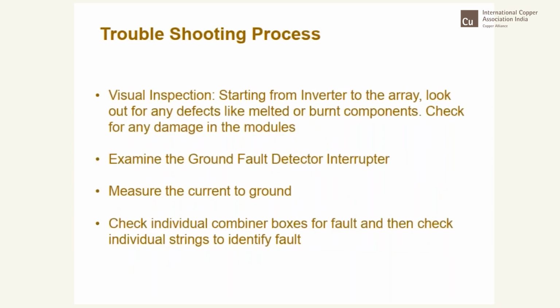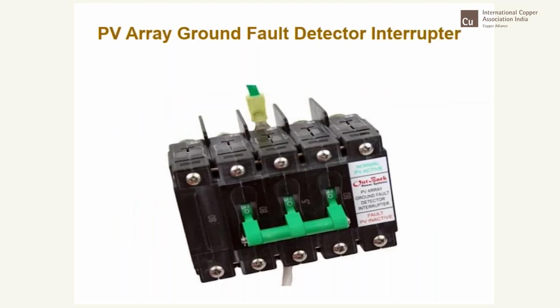So troubleshooting: visual inspection, and then examining the ground fault detector interrupter, measuring the current to ground, checking individual combiner boxes for fault, and then taking appropriate action. So these are ground fault detector interrupters.